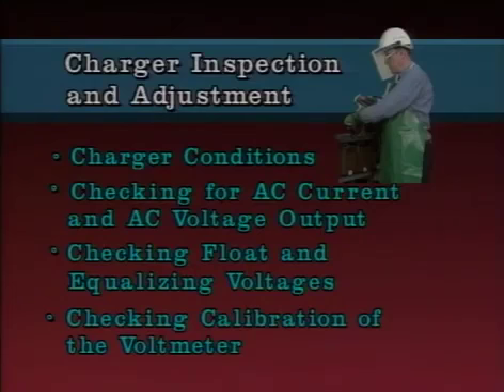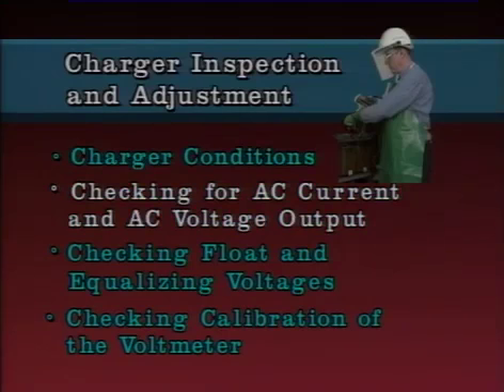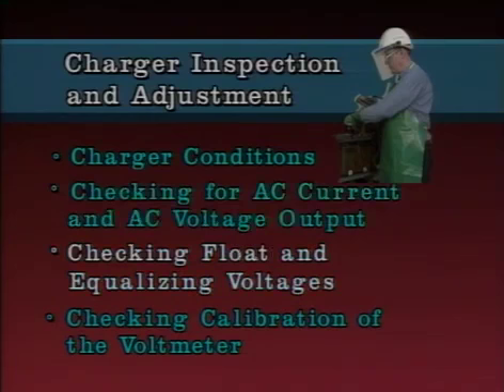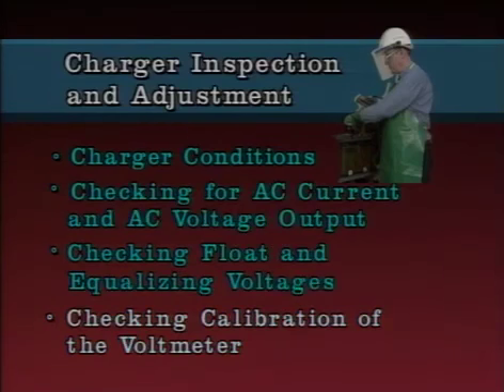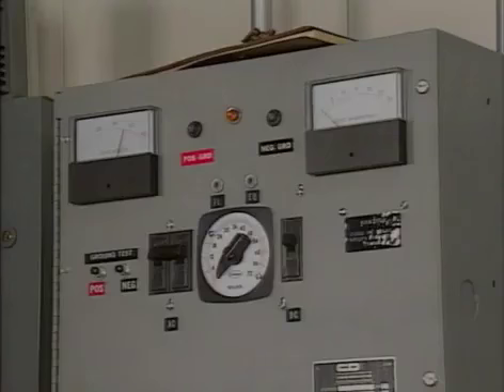The key points that will be covered include inspecting general charger conditions, checking for AC current and AC voltage output from the charger, checking float and equalizing voltages, and checking the calibration of the charger's voltmeter.